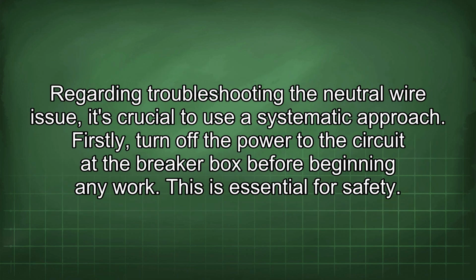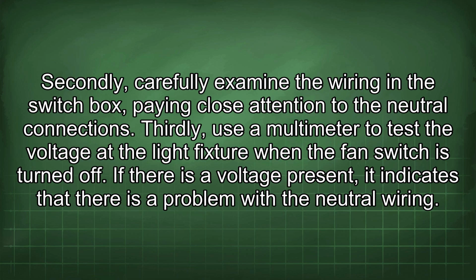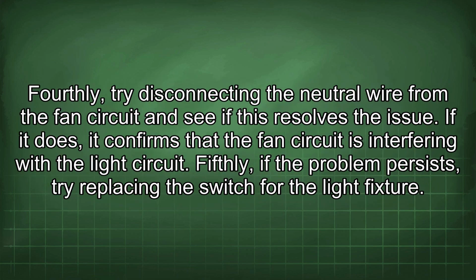Regarding troubleshooting the neutral wire issue, it's crucial to use a systematic approach. Firstly, turn off the power to the circuit at the breaker box before beginning any work. This is essential for safety. Secondly, carefully examine the wiring in the switch box, paying close attention to the neutral connections. Thirdly, use a multimeter to test the voltage at the light fixture when the fan switch is turned off. If there is a voltage present, it indicates that there is a problem with the neutral wiring. Fourthly, try disconnecting the neutral wire from the fan circuit and see if this resolves the issue. If it does, it confirms that the fan circuit is interfering with the light circuit.